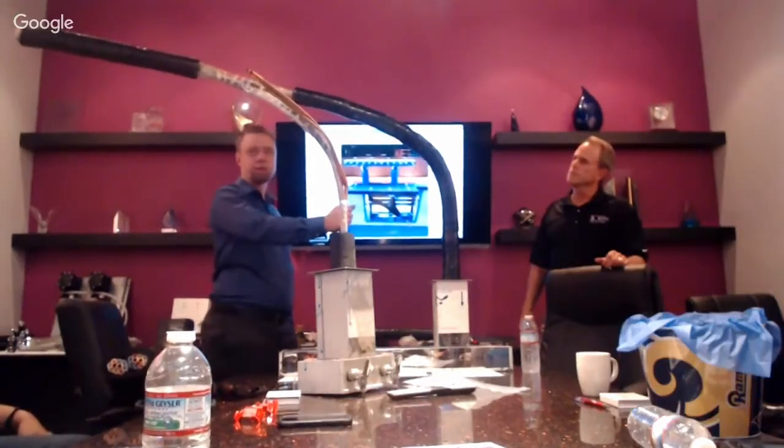They'll stop. If they're pouring nonstop, they may never know. But when it sits, all it takes is a small section that's not refrigerated for them to have a problem with foaming. And it'll be intermittent. They'll complain about it for months. They'll say this hasn't worked since the day we opened. So it's really important for the installers to have access to all the areas that they need to work in.